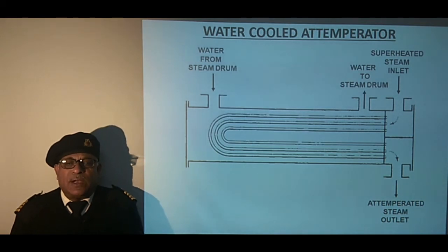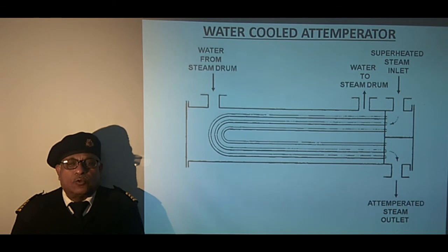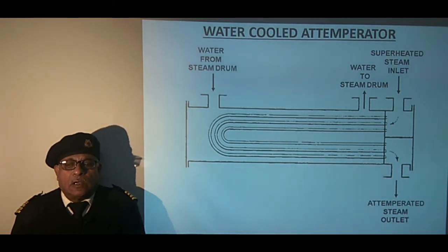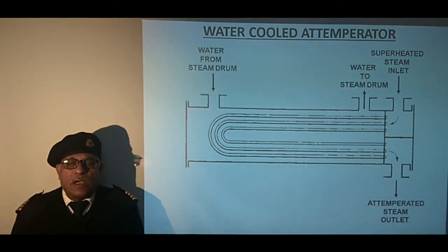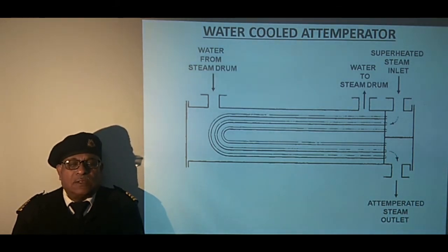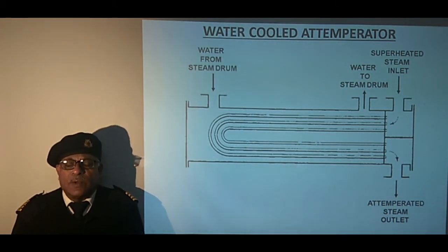This attemperator is of shell and tube type, in which U-tubes are attached to the header which has steam inlet and outlet connections. The cylindrical shell has water inlet and outlet connections from the steam drum. The incoming water gets heated by the steam passing through the U-tubes. The temperature difference at the two ends causes the circulation of water through the steam drum, so this arrangement is used in some boilers.